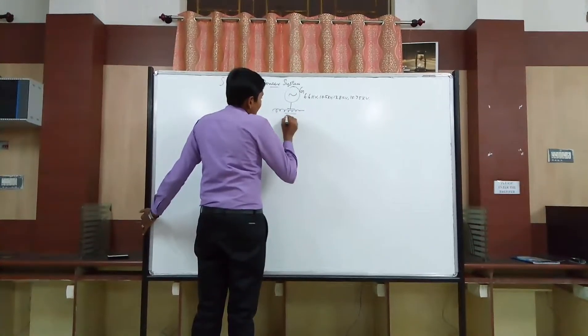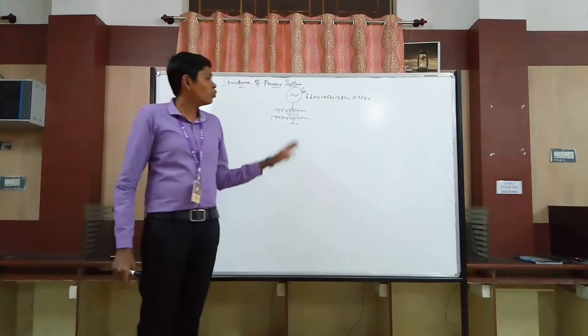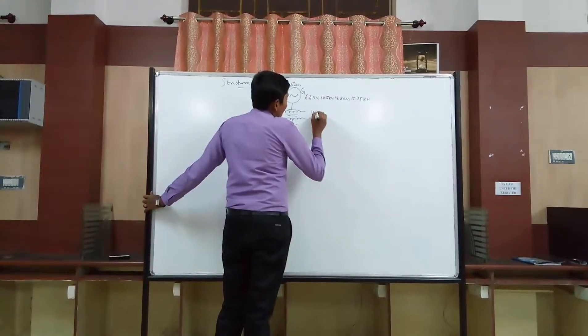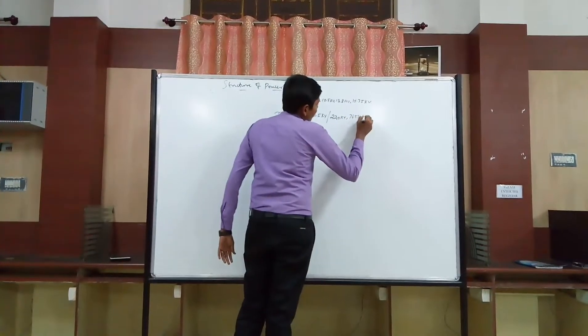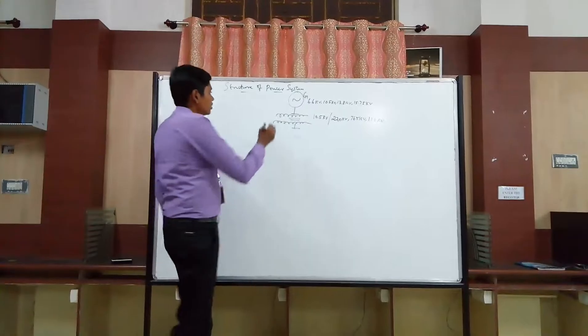Next to this, we are having a step-up transformer. The main reason that we are having a step-up transformer on the generation side is to minimize the losses. In the step-up transformer, for example, if we take 10.5 KV, it can be stepped up to 220 KV, 765 KV, or 110 KV. These are the step-up ranges we are using with the step-up transformer.